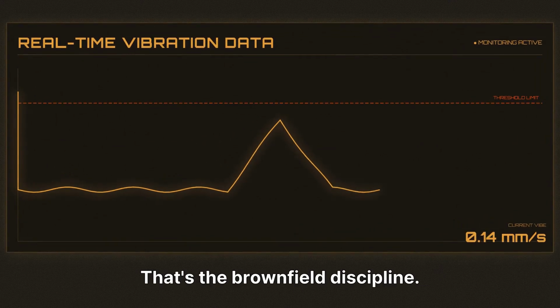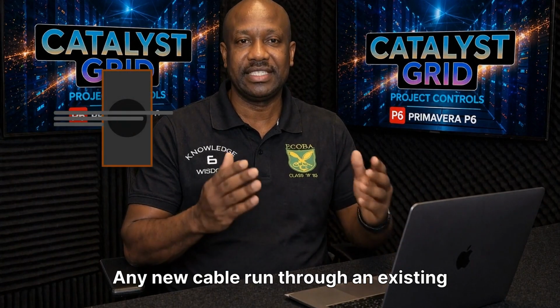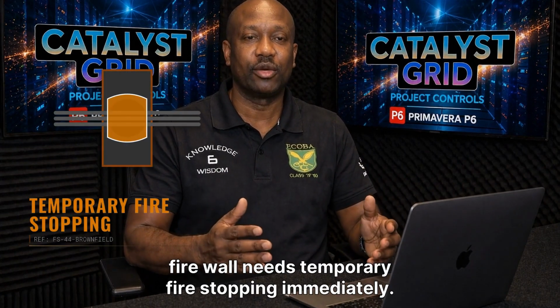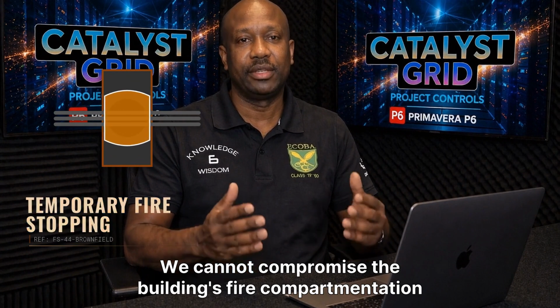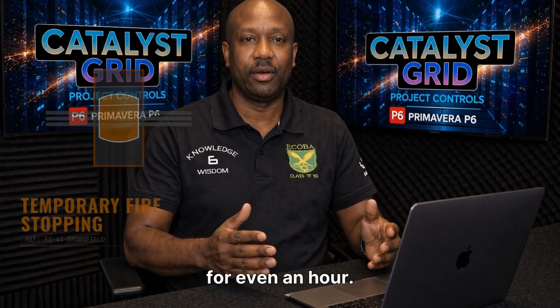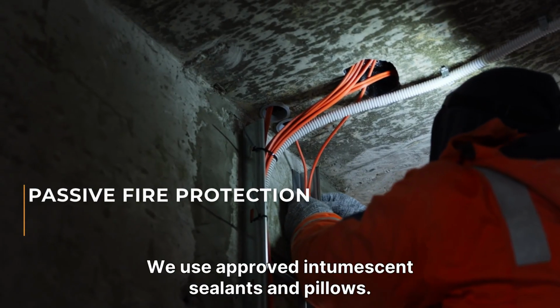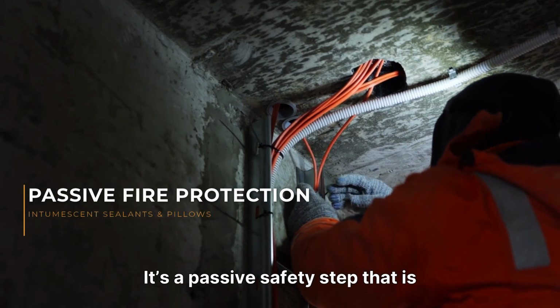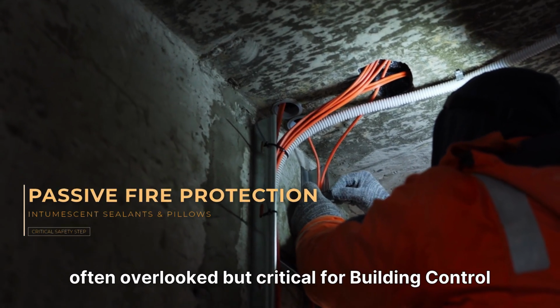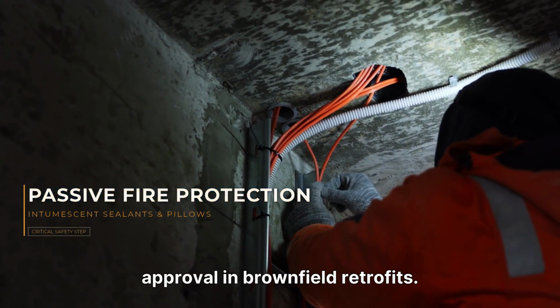That's the Brownfield discipline. Any new cable run through an existing firewall needs temporary fire stopping immediately. We cannot compromise the building's fire compartmentation for even an hour. We use approved intumescent sealants and pillows. It's a passive safety step that is often overlooked, but critical for building control approval in brownfield retrofits.